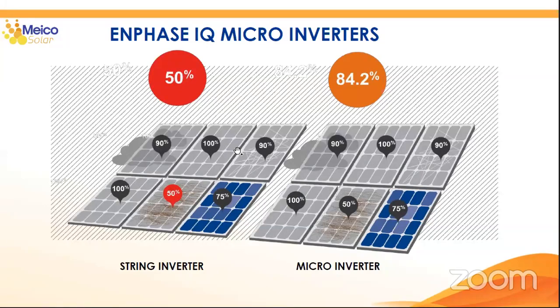So in this case, the string inverter will set the MPPT, the tracking of the maximum point of power, to the lowest module in that string. So when you have this, you will have a complete efficiency and power generation of only 50%, even if other modules that are working perfectly could make 100%, okay? In the right side is the same scenario. The only difference is you're not having a string inverter, you're only having one microinverter per module. In this case, each module is a complete independent world. So what happens to this module doesn't make any difference to the one next to it.